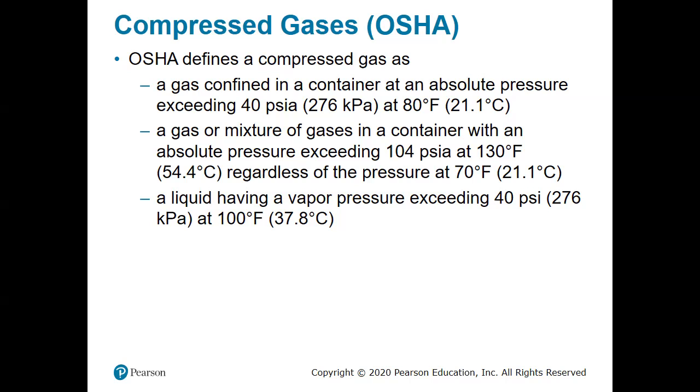Or this third definition, a liquid having a vapor pressure above 40 psi at 100 Fahrenheit. And remember, we saw this definition when we were talking about the definition of a flammable liquid. The reason we have the threshold of 40 psi at 100 Fahrenheit is because if it goes above 40 psi, then we're talking about a gas.